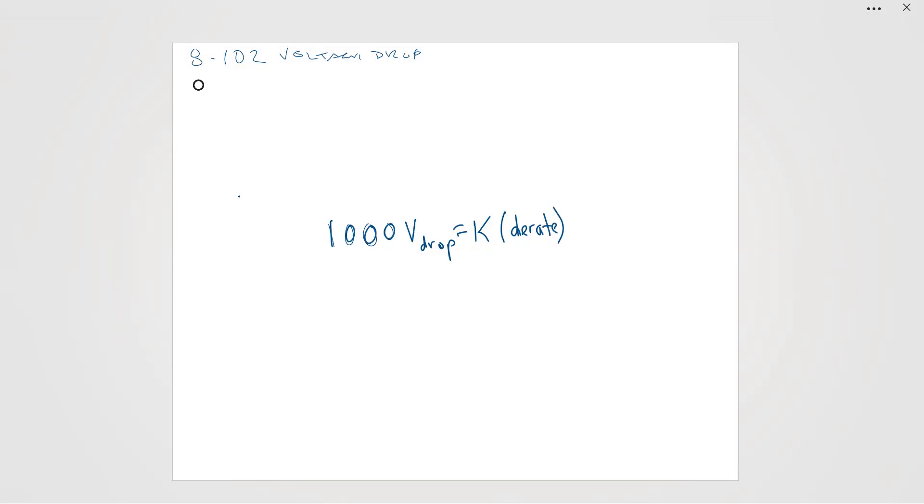I'm just going to call it derate because we can call variables whatever we want, times F, which is the F factor that you see in table D3 from note two, times the current, which is the load current in amps, times the L, which is the conductor length in meters.